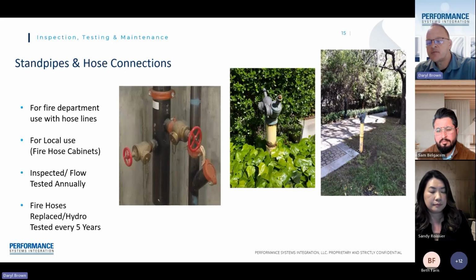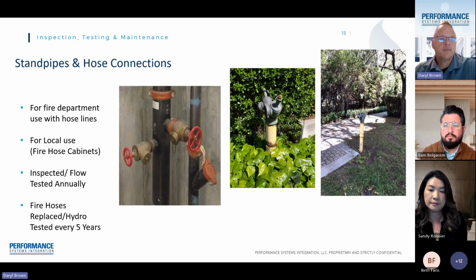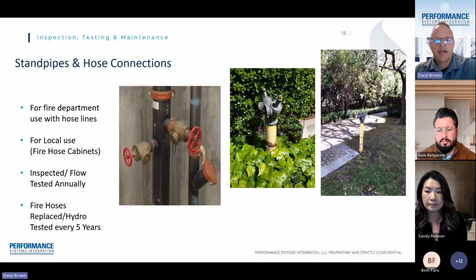Next, we have standpipes or hose connections. Basically, these are piping systems that are utilized for taking water and supplying water to fire department connections. These fire department connections are utilized by the fire department in case there is a fire. It gives them a water source for fighting the fire. The fire department will hook up their hoses to these connections for obtaining water to fight any kind of fire. On the left-hand side, you'll see the most common standpipe systems that you'll see in most commercial buildings. These will also be in the stairwells. In the middle and on the right, these are more of a residential or horizontal standpipe system.